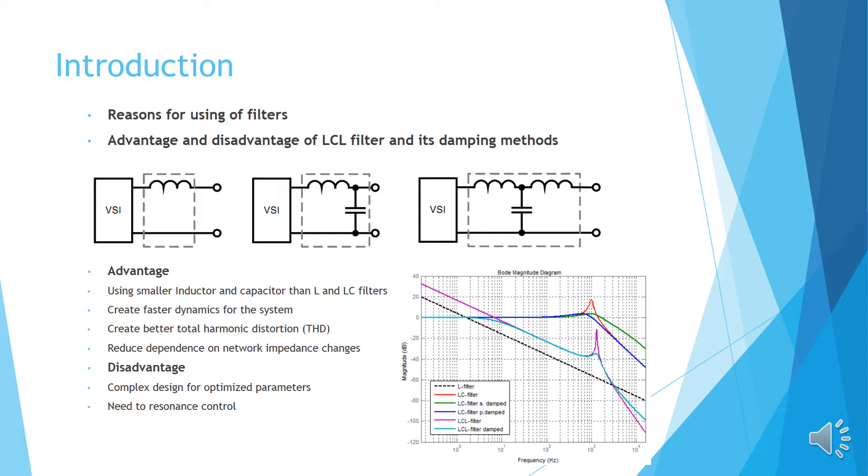Advantages of L-CL filters and other passive filters, such as using smaller inductor and capacitors, create faster dynamics for the system, create better total harmonic distortion or THD, reduce dependence on network impedance. Disadvantages of L-CL filters, such as complex design for optimized parameters, need for resonance control.